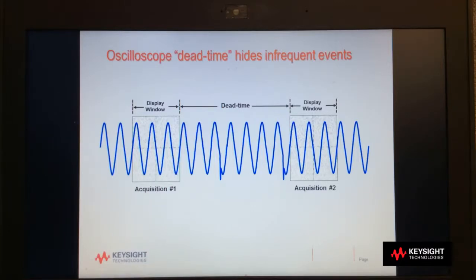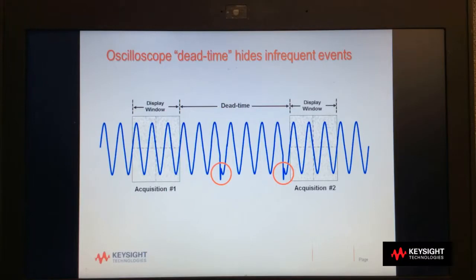All scopes have dead time, some more than others. But as you can see, here two glitches occurred during the scope's dead time, which means that the scope missed them.